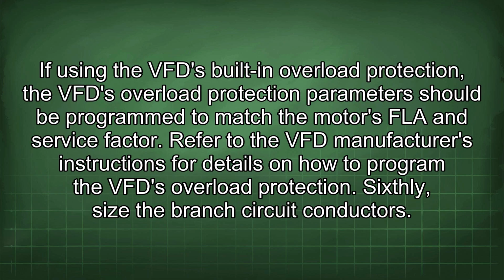If using the VFD built-in overload protection, the VFD overload protection parameters should be programmed to match the motor's FLA and service factor. Refer to the VFD manufacturer's instructions for details on how to program the VFD overload protection.